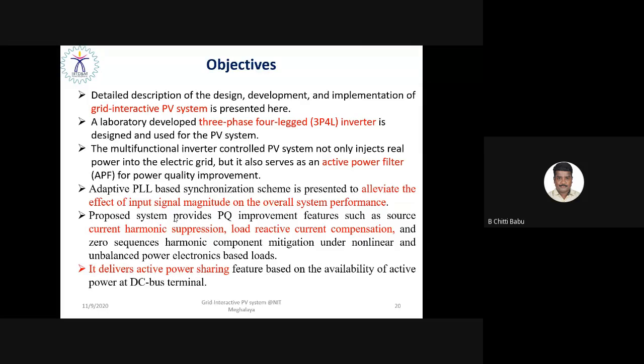So the objectives of the research, and what our team has done: we have implemented different advanced control strategies for a grid-tied solar PV system. The detailed description of the design, development, and implementation of the grid interactive solar PV system is presented here. For that, an elaborate prototype of a three-phase four-legged inverter is designed and used for the PV system. The proposed three-phase four-legged inverter can act as a multifunctional inverter, able to independently control active as well as reactive power for voltage and frequency control. It also serves as an active power filter for mitigating lower order harmonics injected into the utility grid. So it not only controls active and reactive power, it also acts as a shunt active power filter, so that overall system performance is enhanced.